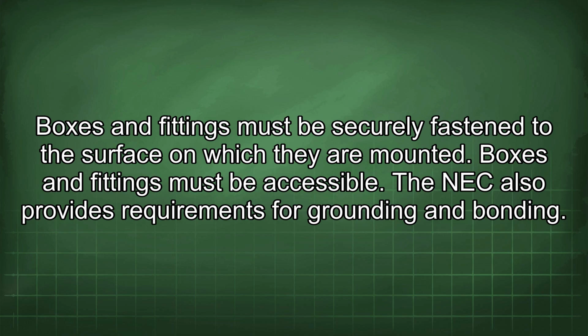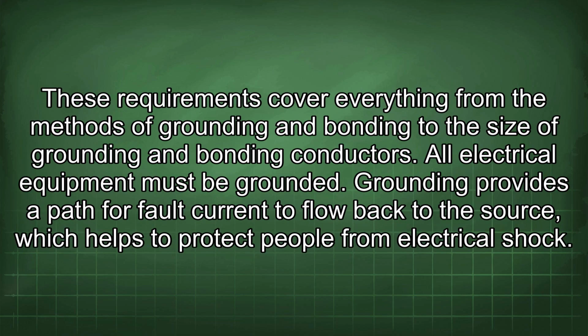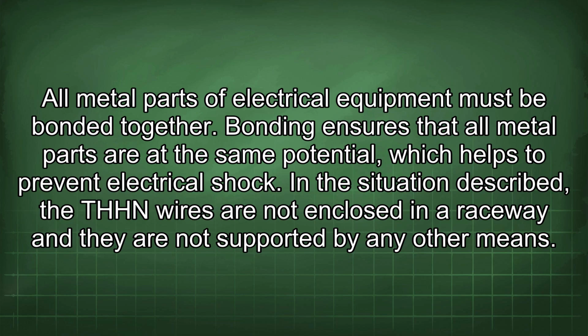The NEC also provides requirements for grounding and bonding. These requirements cover everything from the methods of grounding and bonding to the size of grounding and bonding conductors. All electrical equipment must be grounded. Grounding provides a path for fault current to flow back to the source, which helps to protect people from electrical shock. All metal parts of electrical equipment must be bonded together. Bonding ensures that all metal parts are at the same potential, which helps to prevent electrical shock.